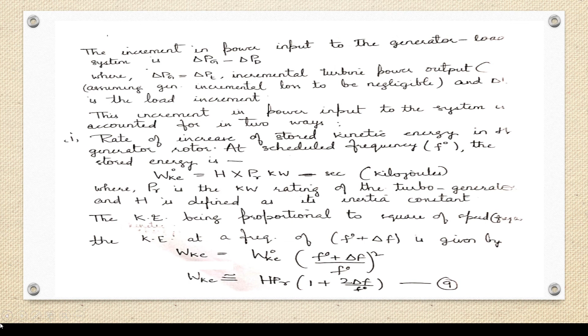Kinetic energy being proportional to square of the speed or square of the frequency, the kinetic energy at a frequency of F0 plus delta F will be given by WKE is equal to WKE naught into (F0 plus delta F by F0) square. Okay. So because kinetic energy is proportional to the square of the frequency, we are writing here now kinetic energy at a frequency of F naught plus delta F. That is Wk is equal to Wke naught into (F naught plus delta F by F naught) square, or Wk is approximately equal to H PR (1 plus 2 delta F by F naught).